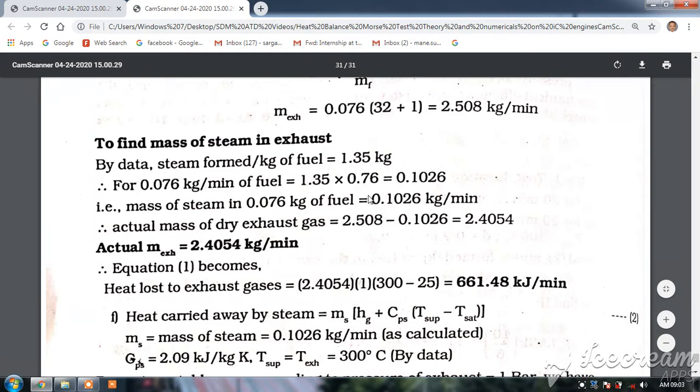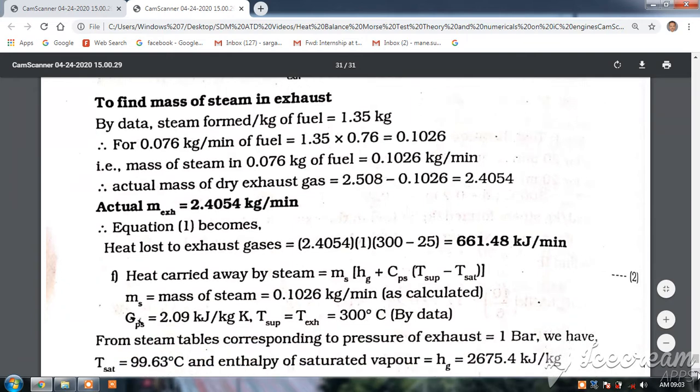Actual mass of dry gases is 2.5 - 0.1026 = 2.4 kg per minute. So heat loss to exhaust gases is m × c_p × ΔT = 2.4 × 1 × (300 - 25) = 661 kilojoules per minute.